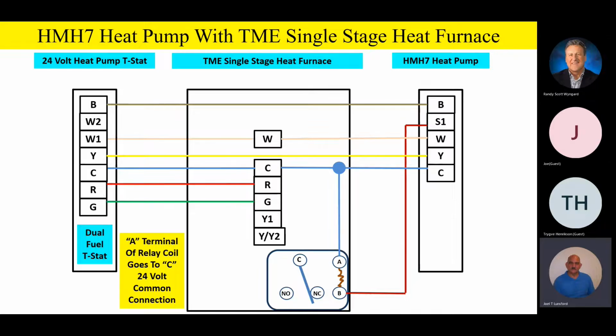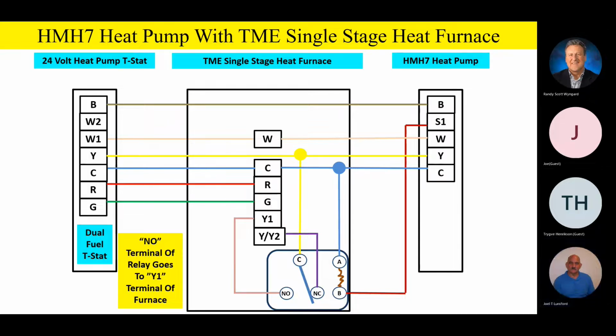Now watch this, because the terminals are a little bit different. We're going to see that the 24-volt common on the switching relay itself is still going to go to the C terminal like we had before, but you're going to notice that your normally closed contact is now going to go over to a terminal on the furnace that says Y/Y2. Automatically, Y/Y2 is high-speed airflow. So high-speed cooling airflow, Y/Y2, will be on our normally closed contact on the relay. You'll notice that the normally open contact on the relay will go up to Y1, and that Y1 is our first stage cooling call on our furnace product.